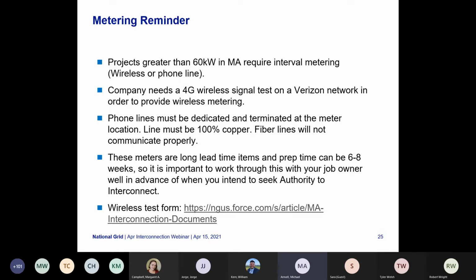The phone lines, if you cannot have a wireless system, the phone lines must be dedicated and terminated at the meter location. The line must be 100% copper. Fiber lines will not communicate properly. These meters are long lead time items, and prep time can be 6 to 8 weeks. So it's important to work through this with the job owner well in advance of when you intend to seek the authority to interconnect. There's a link here for the wireless test form, which will be within the case. At that point, you can upload your screenshot and complete the form for us to have the meter programmed.